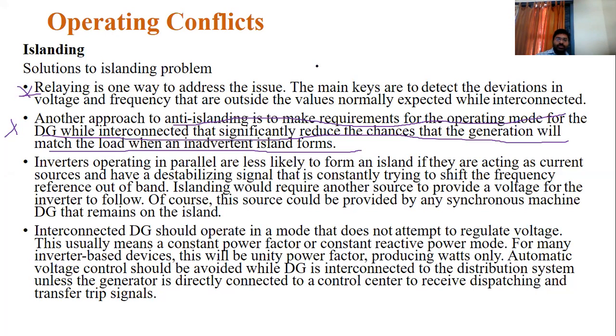Okay, now? Yes, you understand this? An anti-islanding approach. What is the solution here? What is the anti-islanding approach? The first one is where the connected DG matches the load requirements. And the second approach: inverters operating in parallel are less likely to form an island. Most of the DGs in this system are connected in parallel, which may lead to reduced islanding properties.